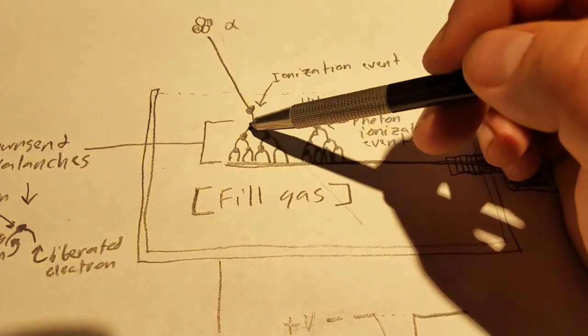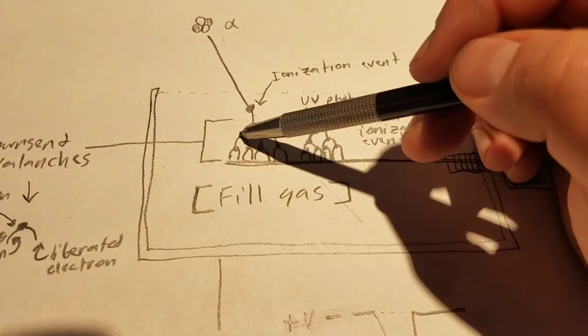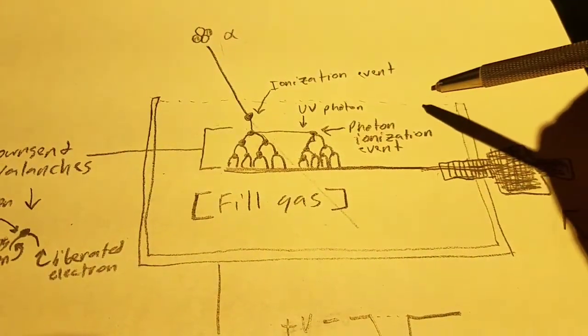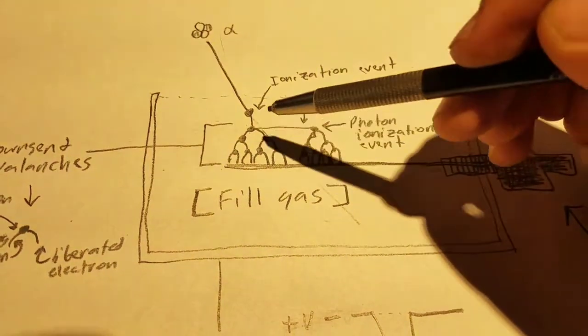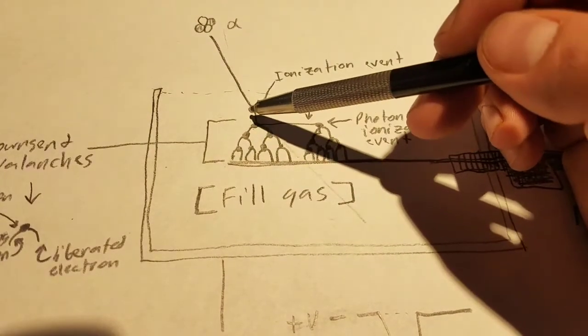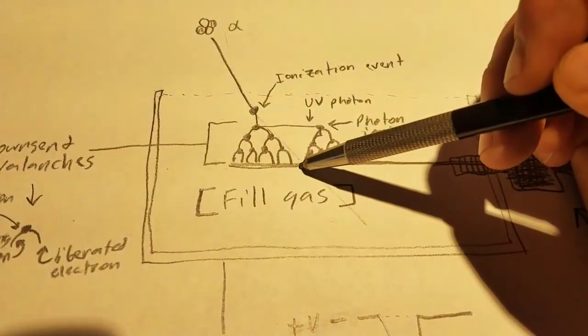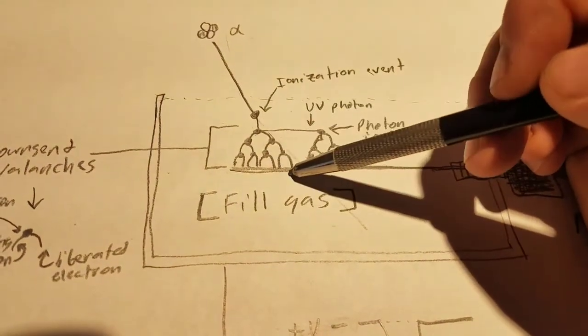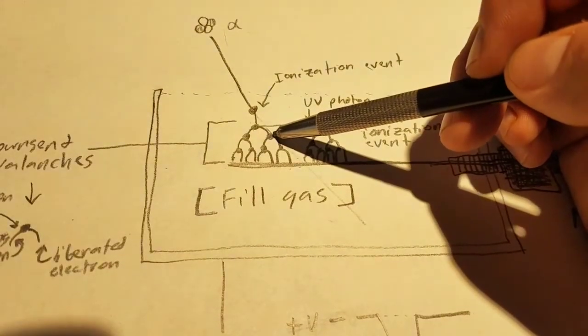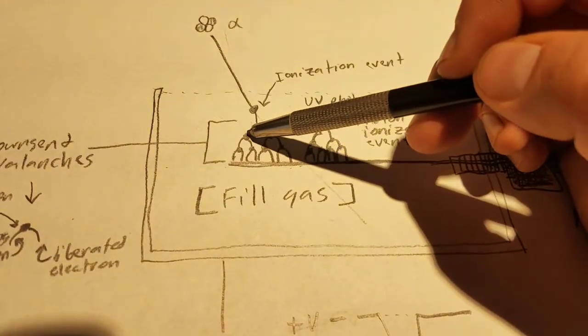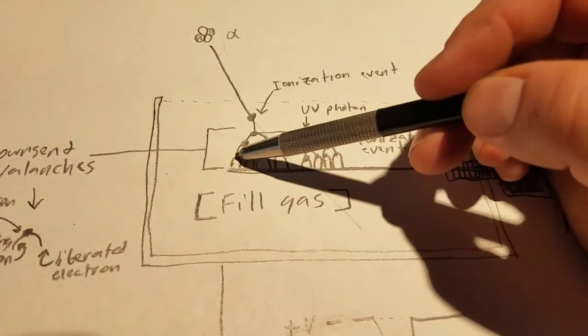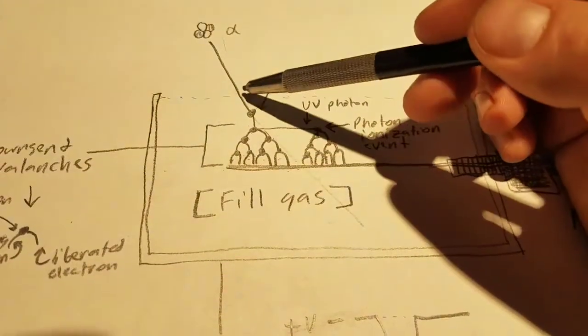It causes electrons to split off, and because there's a 900 volt potential between this and the casing, it'll actually cause the electrons to accelerate towards the anode because it has a positive charge and electrons have a negative charge. While that's happening, the ions created strike other atoms in here and break off additional electrons, causing several other ionization events.